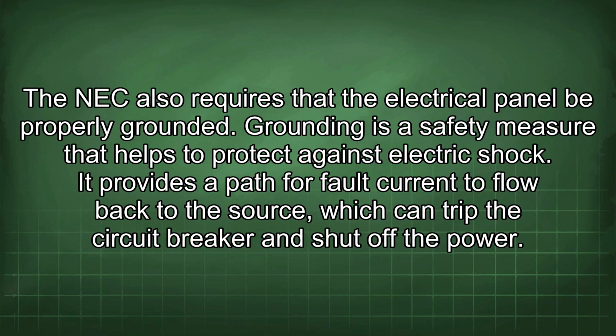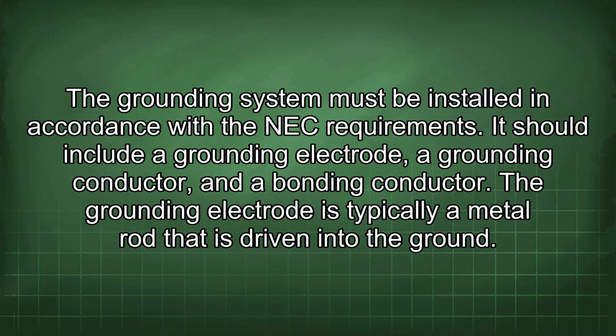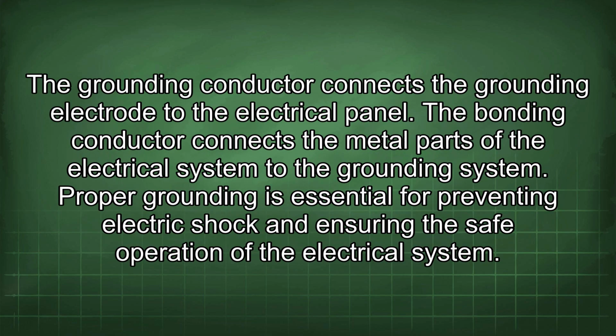The NEC also requires that the electrical panel be properly grounded. Grounding is a safety measure that helps to protect against electric shock. It provides a path for fault current to flow back to the source, which can trip the circuit breaker and shut off the power. The grounding system must be installed in accordance with the NEC requirements. It should include a grounding electrode, a grounding conductor, and a bonding conductor. The grounding electrode is typically a metal rod that is driven into the ground. The grounding conductor connects the grounding electrode to the electrical panel. The bonding conductor connects the metal parts of the electrical system to the grounding system. Proper grounding is essential for preventing electric shock and ensuring the safe operation of the electrical system.